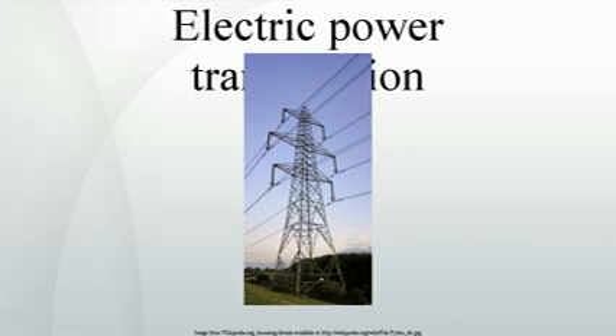The ratio of real power, transmitted to the load, to apparent power, the sum of real and reactive, is the power factor. As reactive current increases, the reactive power increases and the power factor decreases. For transmission systems with low power factor, losses are higher than for systems with high power factor. Utilities add capacitor banks, reactors and other components, such as phase-shifting transformers, static VAR compensators, physical transposition of the phase conductors, and flexible AC transmission systems, FACTS, throughout the system to compensate for the reactive power flow and reduce the losses in power transmission and stabilize system voltages. These measures are collectively called reactive support.